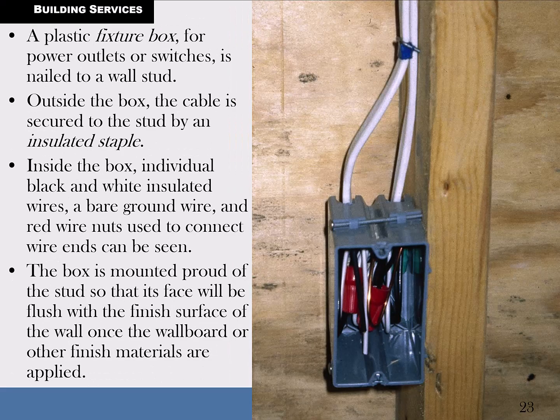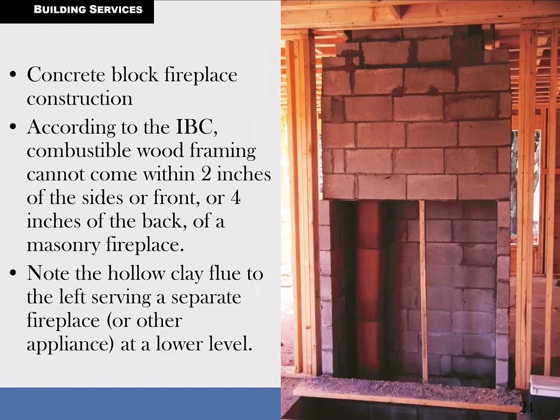We can often get away with plastic fixtures in residential construction, but in commercial and industrial construction we typically have to use metal boxes, and particularly with industrial construction, metal conduit, maybe some BX cable, which is a metal woven spun jacket that protects, and also builds up protection from the electrical field generated with the voltage and amperage.